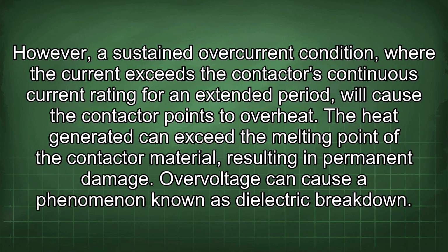However, a sustained overcurrent condition, where the current exceeds the contactor's continuous current rating for an extended period, will cause the contactor points to overheat. The heat generated can exceed the melting point of the contactor material, resulting in permanent damage. Overvoltage can cause a phenomenon known as dielectric breakdown.